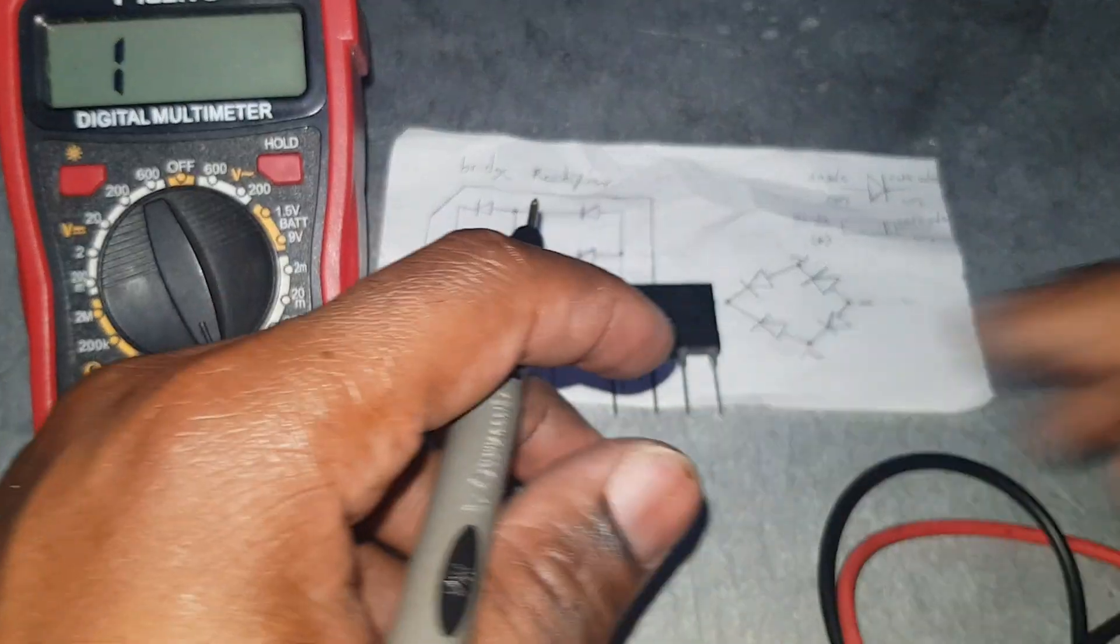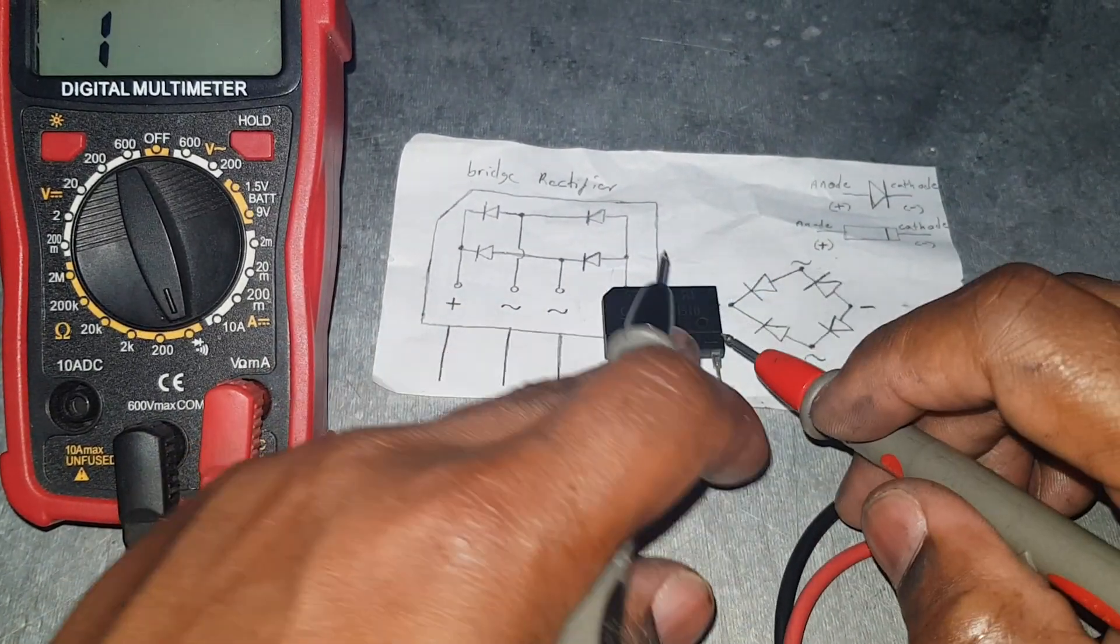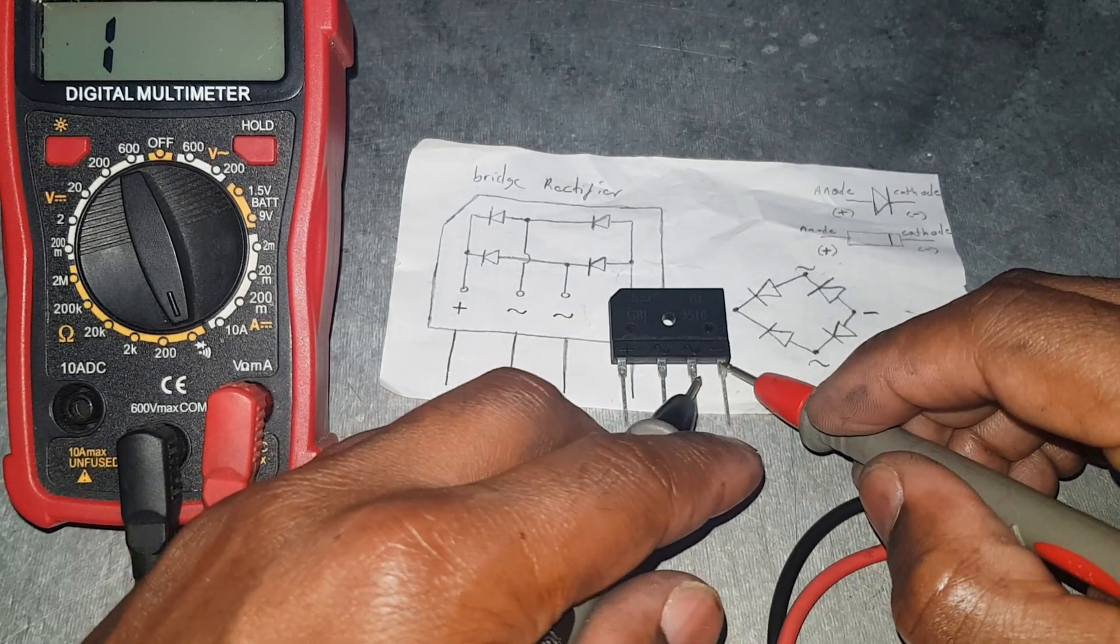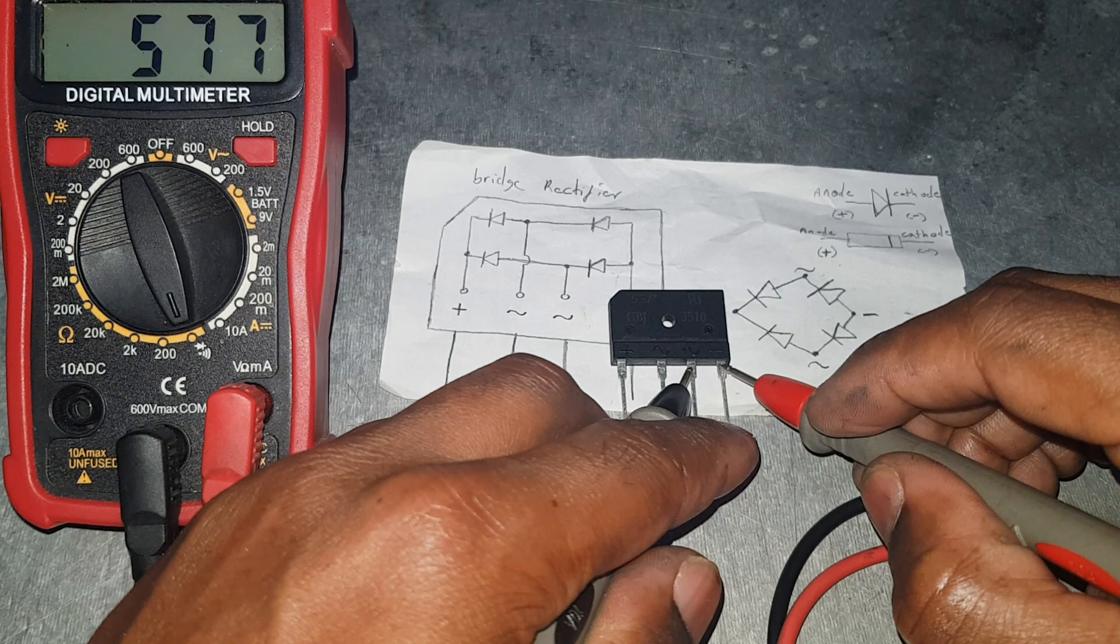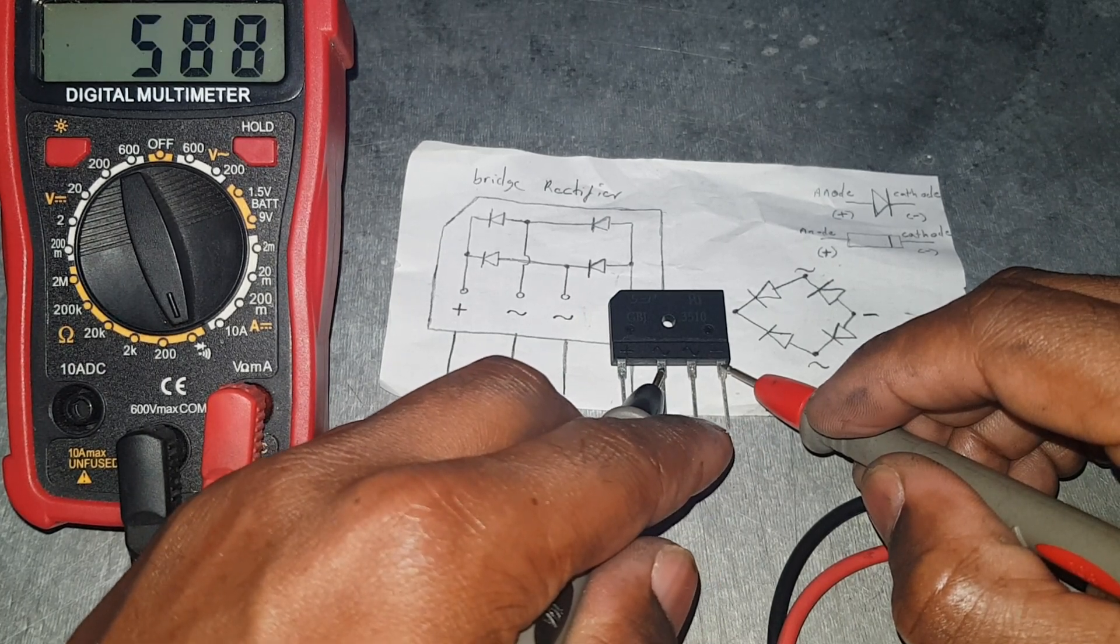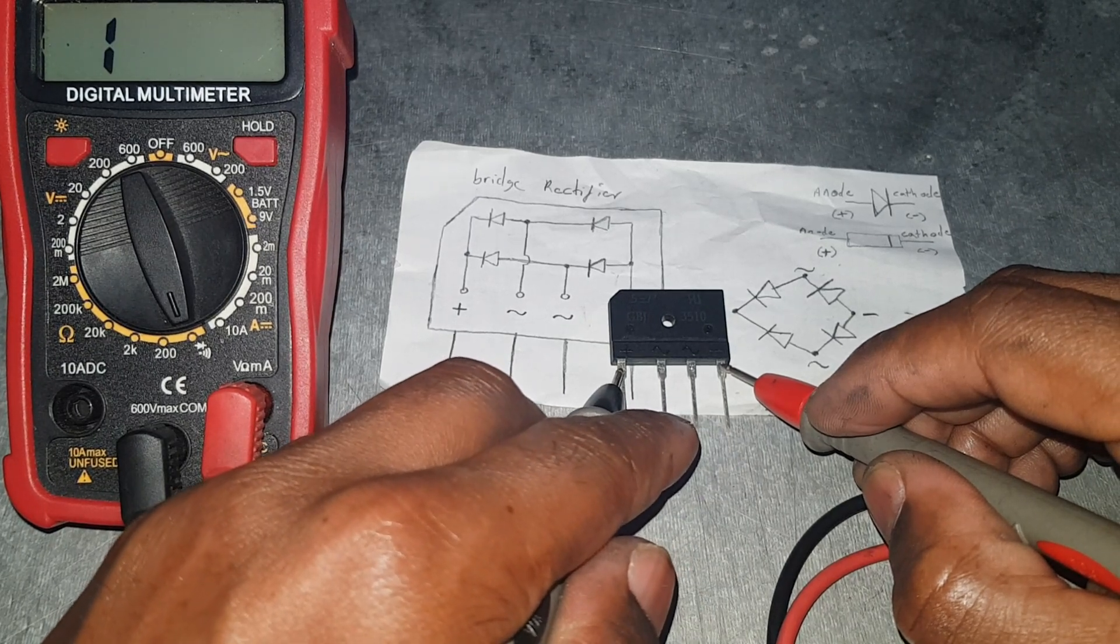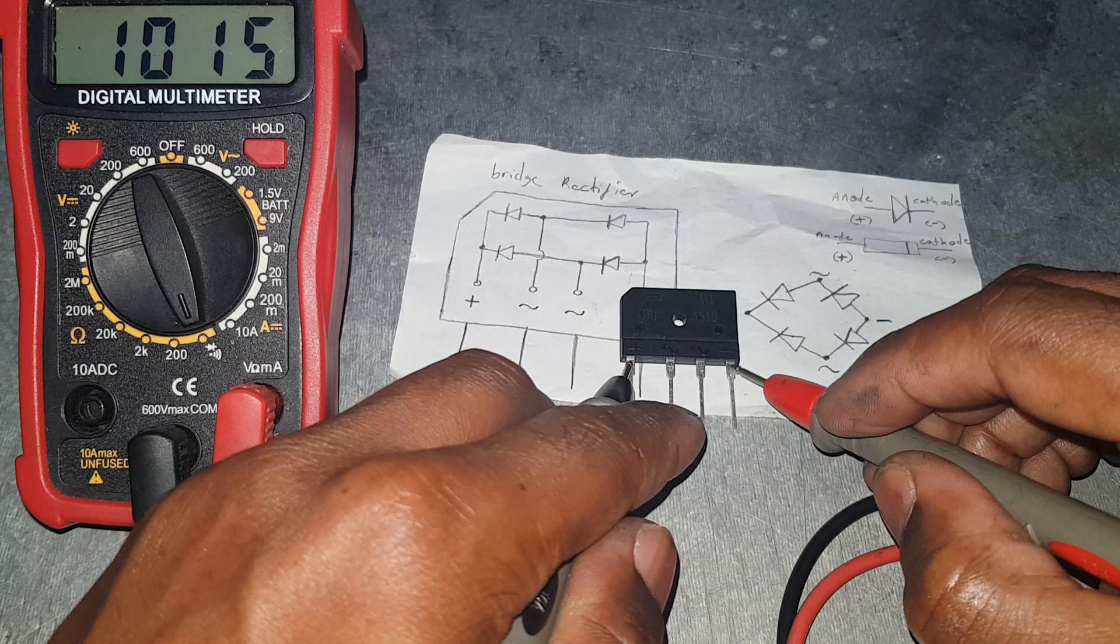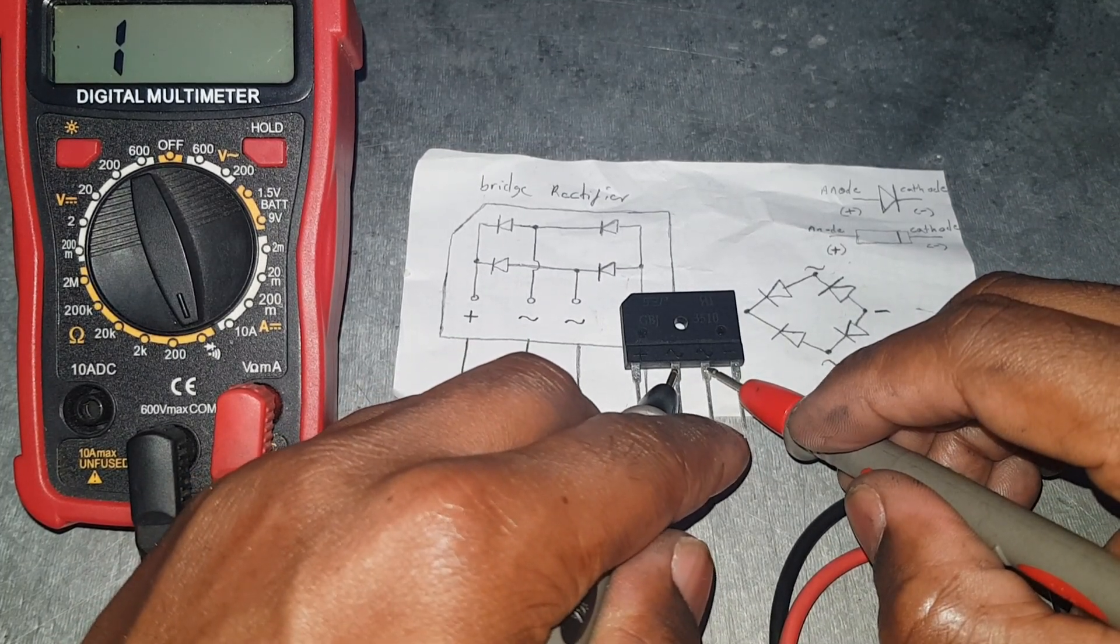We're going to put the positive lead on the negative side of the bridge rectifier here and on one of the next pins right here. You can see we get 577, same thing here. And this last pin here, it should double. We're getting 1015.